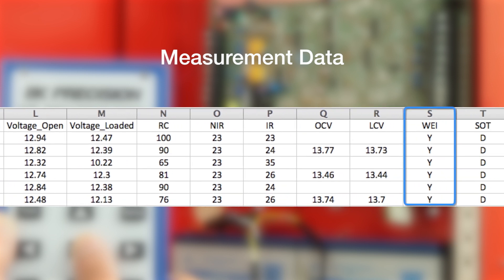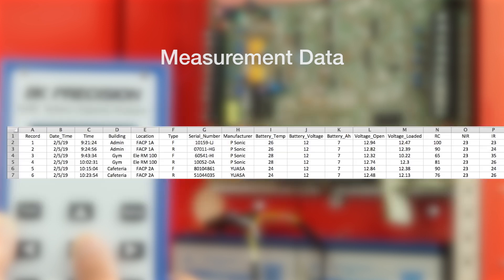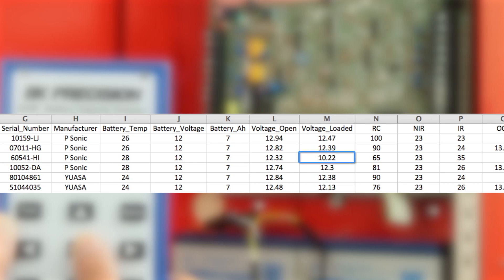Weighting is often enabled for batteries used in critical applications like fire alarm. From this measurement data, battery number 3 has a significant drop in voltage under load and a much higher internal resistance compared to the rest.